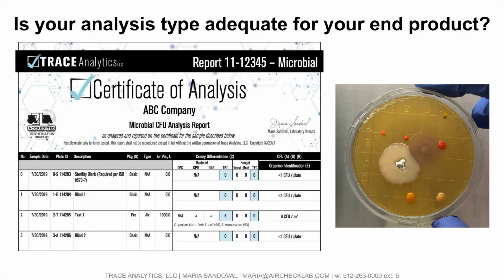You may need to find the source of the gram-negative rod. And so that is invaluable information because now you can go to a filter manufacturer and say, hey, I have these gram-negative rods. They are microorganisms. They are contaminating my compressed air, and I need to find a way to get them out of my piping system. How can I do that?